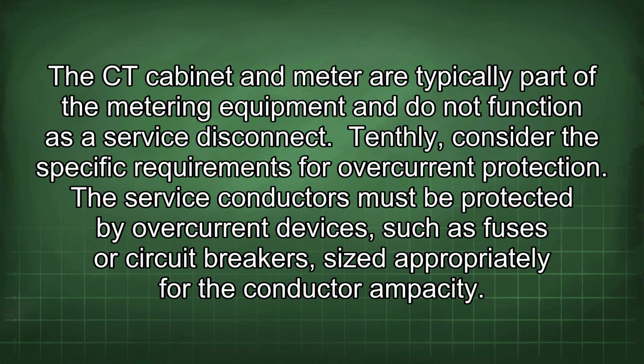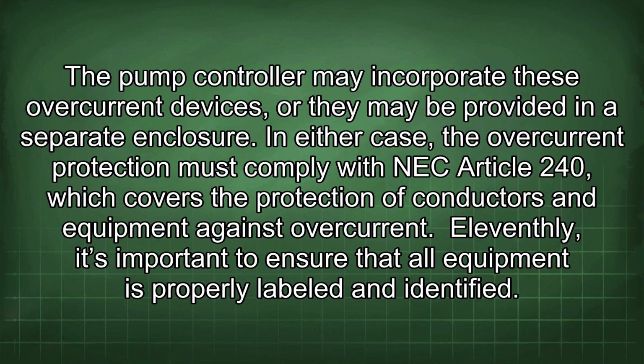The service conductors must be protected by overcurrent devices, such as fuses or circuit breakers, sized appropriately for the conductor ampacity. The pump controller may incorporate these overcurrent devices, or they may be provided in a separate enclosure. In either case, the overcurrent protection must comply with NEC Article 240, which covers the protection of conductors and equipment against overcurrent. 11thly, it's important to ensure that all equipment is properly labeled and identified.